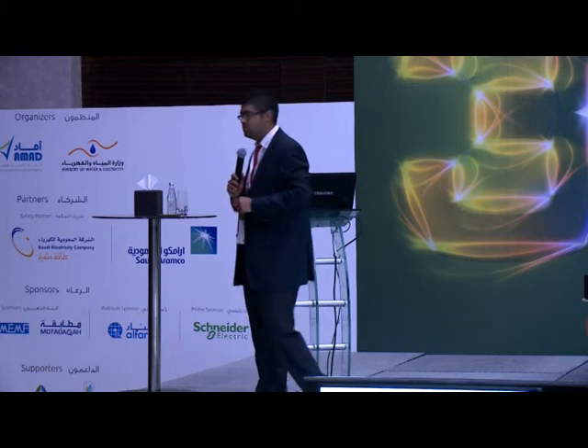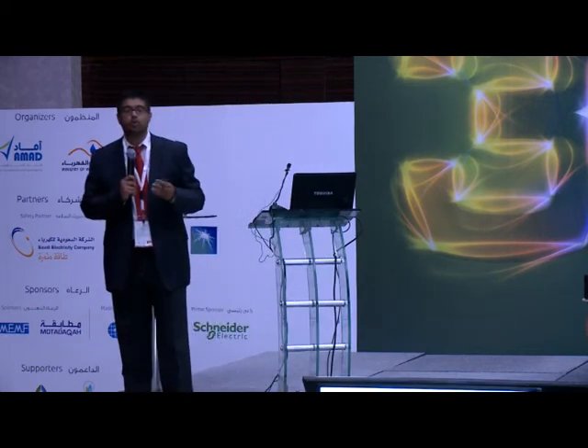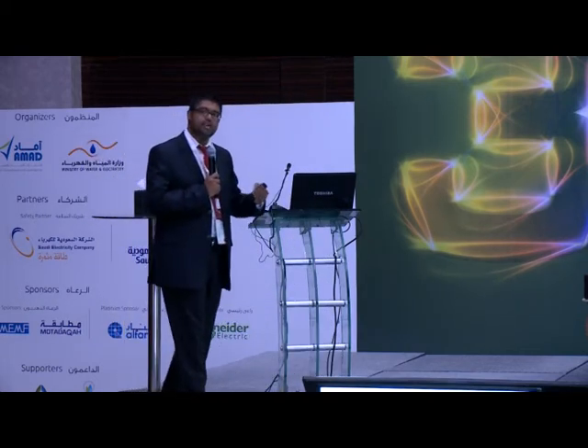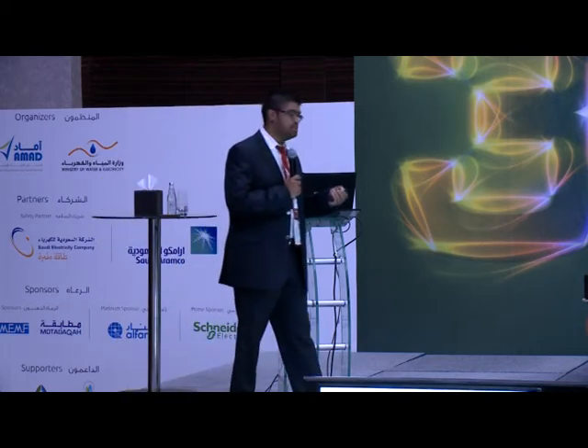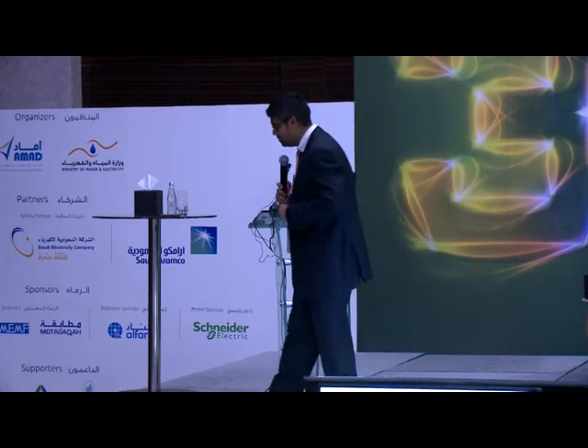Now, ISOLATE simply: the I stands for identify all energy sources, S stands for switch off, O stands for open your disconnects, L stands for lockout, tag out, A stands for, and here's the important one, assure that the contacts are open, visually if possible. T stands for test. That means that we're looking at line testing as well as phase testing on systems that have an earth reference. And most importantly, what we refer to as well in our program is we call for the testing of your equipment.